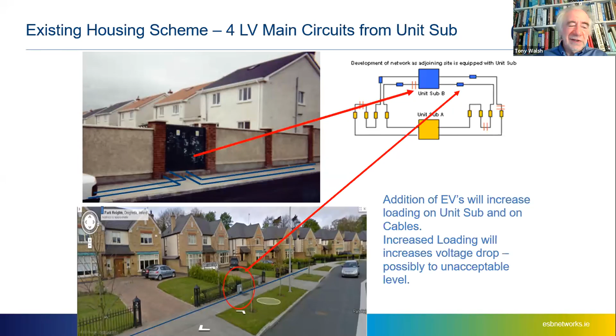So here's a typical housing scheme. We start with the transformer, we've got the mini pillars, we've got the cable circuit. In fact, we have about 4 cable circuits that come out from the substation. We design each house to cope with a peak load of 12 kVA, on the assumption that the average load of the remaining houses is 2.5 kVA.